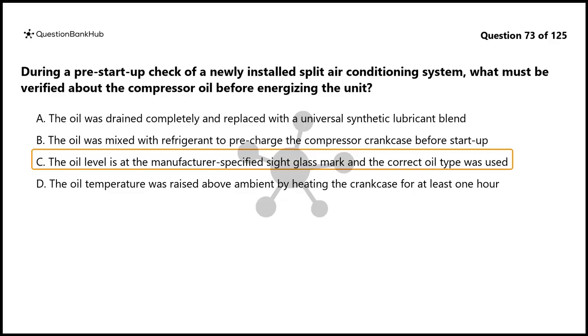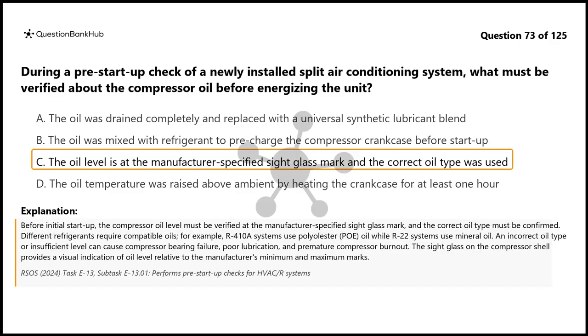The correct answer is C. Before initial startup, the compressor oil level must be verified at the manufacturer-specified sight glass mark, and the correct oil type must be confirmed. Different refrigerants require compatible oils. For example, R410A systems use polyester (POE) oil while R22 systems use mineral oil. An incorrect oil type or insufficient level can cause compressor bearing failure, poor lubrication, and premature compressor burnout. The sight glass on the compressor shell provides a visual indication of oil level relative to the manufacturer's minimum and maximum marks.